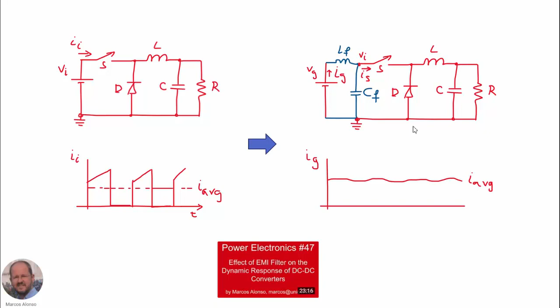So we add an LC filter in order to have at the end, at the input, through the grid, a current that is going to be more or less a DC current with low current ripple. Also, we saw that by adding this filter here, we are going to affect the dynamic response of the whole converter. And in some situations, the operation of the converter can become unstable.